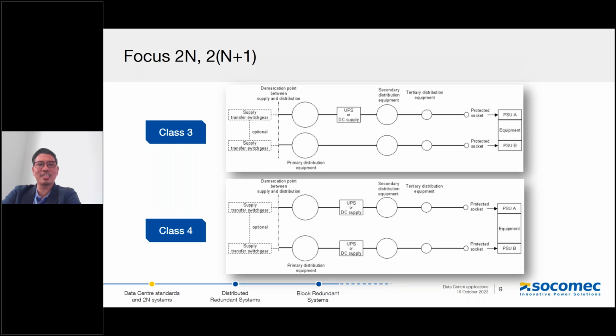As you can see, what's the difference between class 3 and class 4 is, of course, you have two powertrain channels, or we call them channels, channel A and channel B. The main difference between class 3 and class 4 is a UPS on one channel compared to two UPS systems on both. So basically, in a class 4, both A and B channels are live. You can have two active channels running on a class 4, compared to a class 3 where you have a redundant channel that will be brought in for our tier 3 or class 3 application.